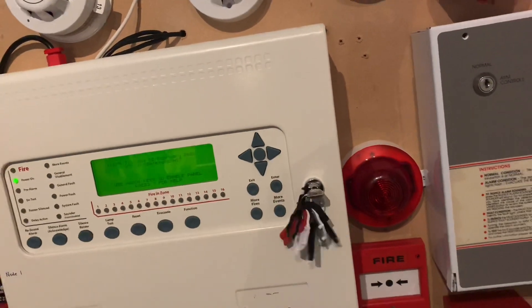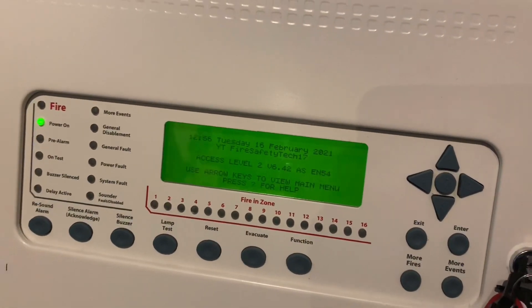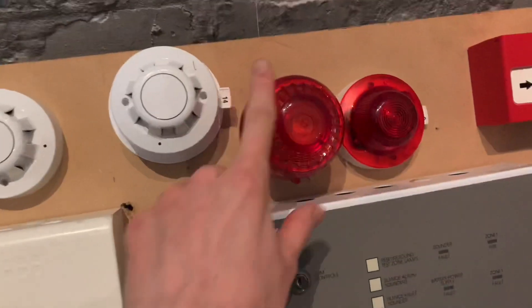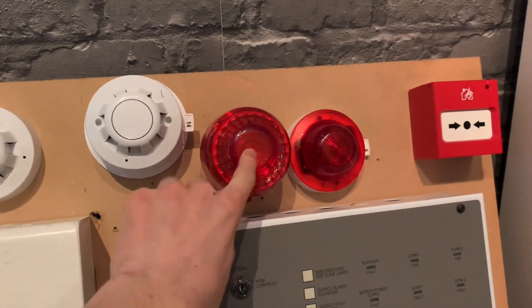Let's get started with the test. We're going to put the panel into access. We're going to be testing the heat detector, the intelligent call point, and also the XP95 open area sounder beacon — this is the Sonos one. The first part of the test will have all sounders enabled, but then we'll disable all the base sounders and just have the open area going.